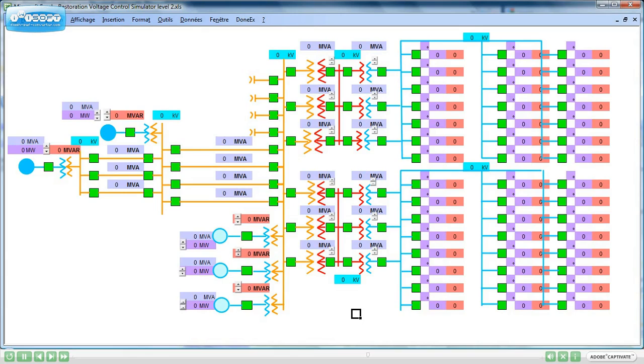Be ready to face voltage alarms. Lines overloaded. Transformers overloaded. When energizing a transformer, be ready to face the transformer magnetization. Let's go for an example. The transformer magnetization will happen in a very short period of time. The users could energize the same transformer thousands of times. There will never be the same effect, due to the remnant magnetic field inside the transformer.